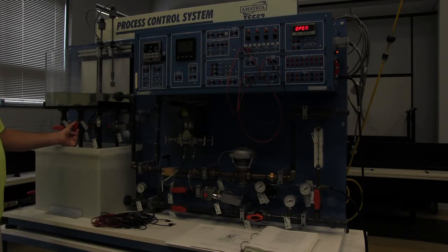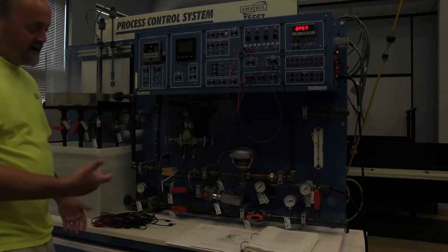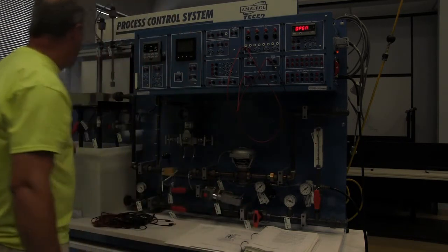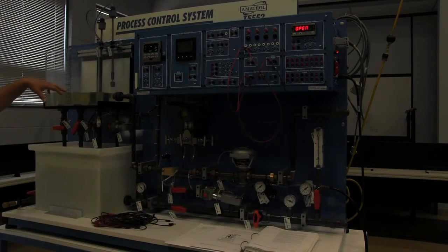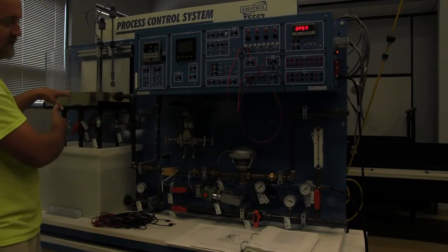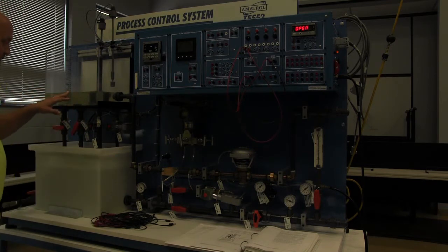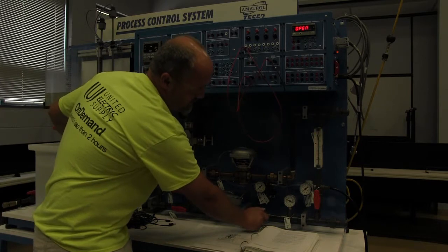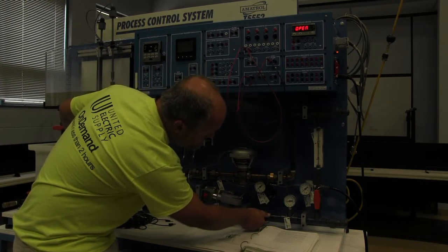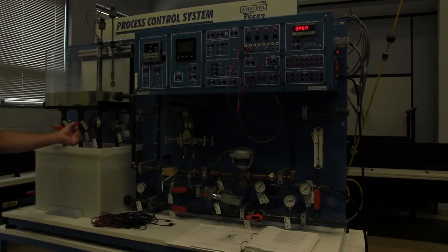So now I'm going to slowly start backing it off, and that is kind of a maintain there. We're maintaining right about 2 inches. So if it's maintaining the system at 1.3 gallons and the pump kicks on and starts giving us more, our tank is going to recover because we're putting more water into the process tank than we are using. If we stay at our 1.3 and demand on the system stops, we'll start increasing in our process tank again. If demand increases, then we will start losing in our process tank.